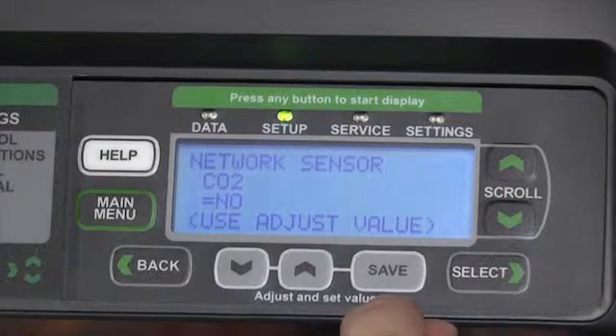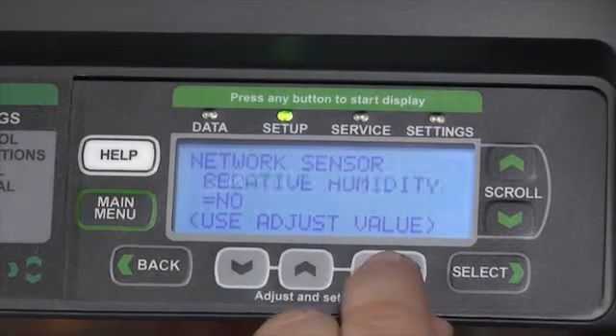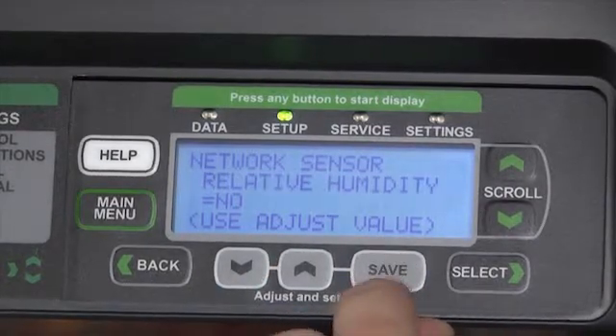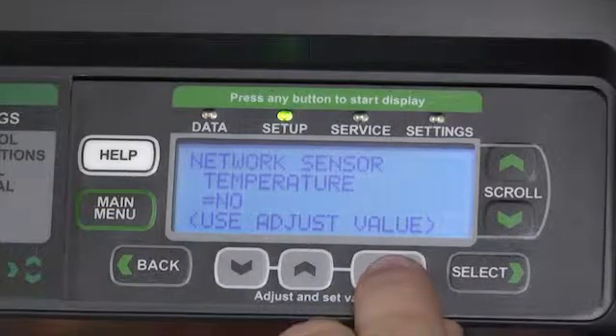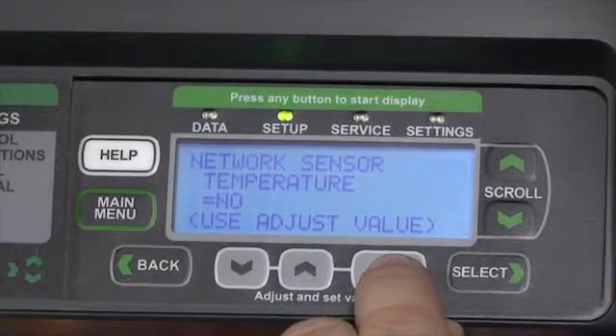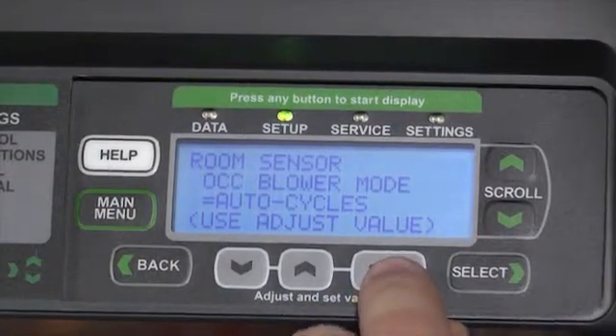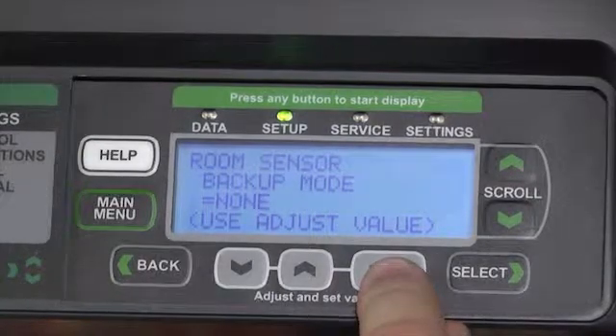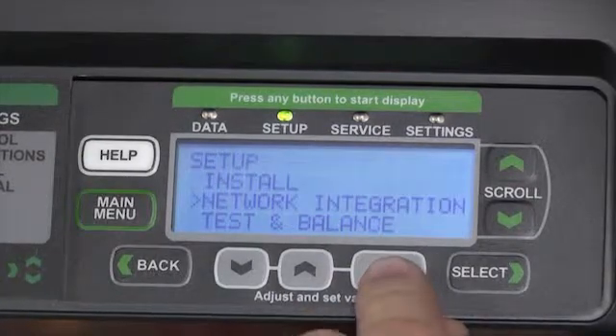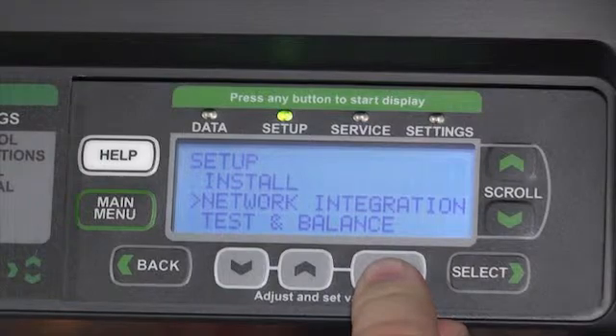We can set if we have a CO2 sensor, a relative humidity sensor, or a network temperature sensor. We can set the occupied blower mode of operation, set our backup mode, and then we'll return back to the network integration screens.